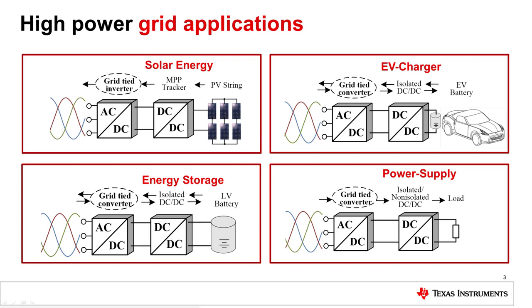The grid tie converter is a bidirectional three-phase power factor corrected AC to DC converter. This allows the converter to take power from the grid or supply power back to the grid. Power factor correction is required to minimize the AC RMS current and limit the current harmonic distortion. The grid tie converter is a very flexible building block for many grid tie power supply applications.